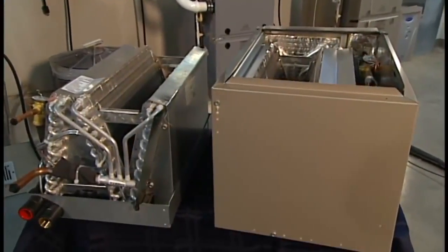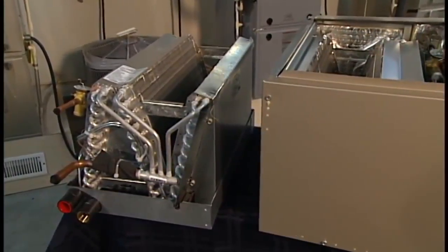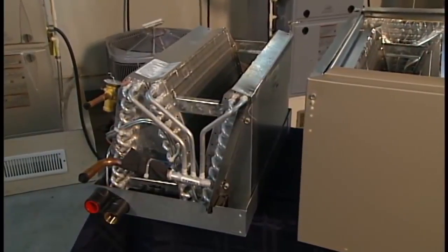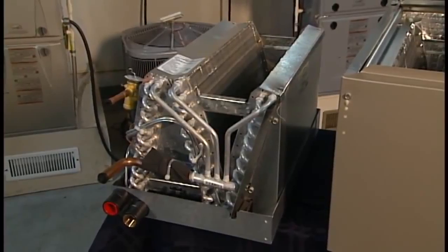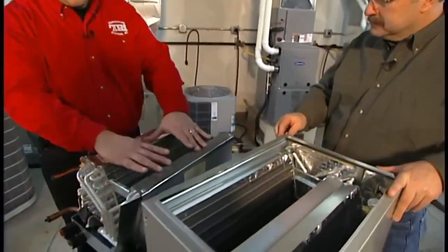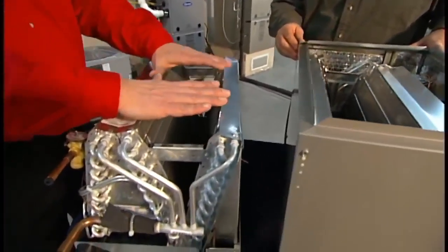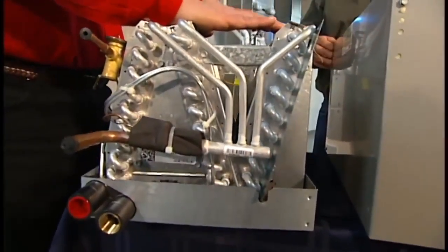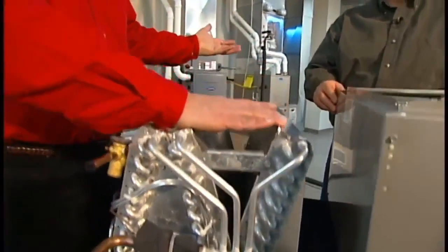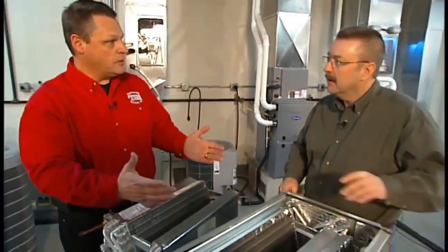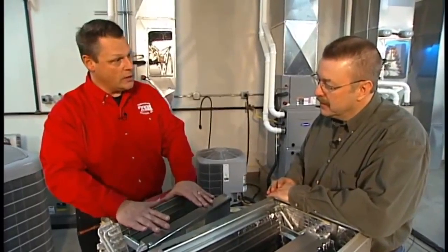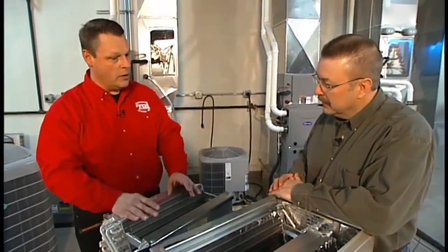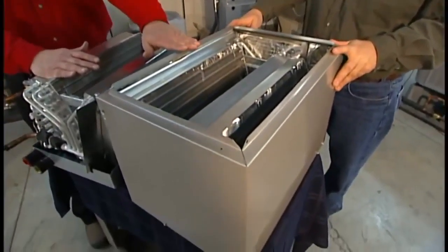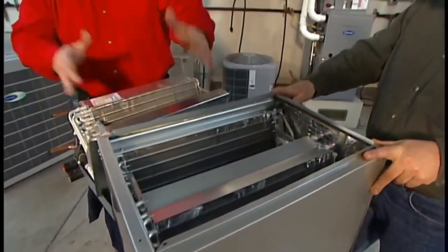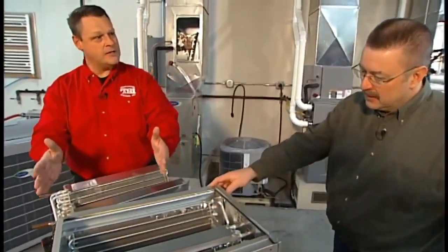Okay, you have some set up over here. They look a little different in shape, but are these also the coil? Yeah, these are still an evaporator coil like we looked at, but with today's efficiencies, we have to come up with a little different configuration to give us more heat transfer surface to get a higher efficiency. This is an N-coil. It happens to not have a casing on it because usually this is used for our retrofit market. In an existing furnace, we may be coming into somebody else's brand. It doesn't necessarily fit as a cased model. So what we would do is come in with an uncased coil, customize the plenum around it, and you're good to go. Whereas if we're replacing a furnace and air conditioner, in most cases, we'll come in with a cased coil that physically matches the fit and finish and size of the furnace it's going to be sitting on.